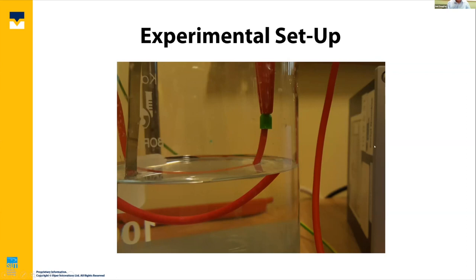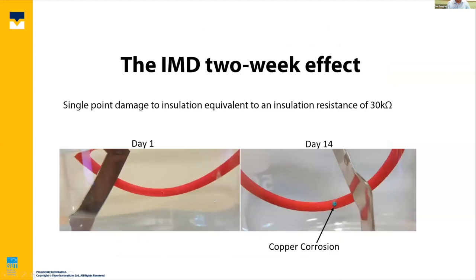And on the right-hand side, this unit that you see here is a line insulation monitoring device, and it is connected to the cable and to this piece of steel. So what we are doing from this device is just driving current through the cable and through this little hole, back up to the earth, and then back to the device. So it's a relatively simple electrical circuit.